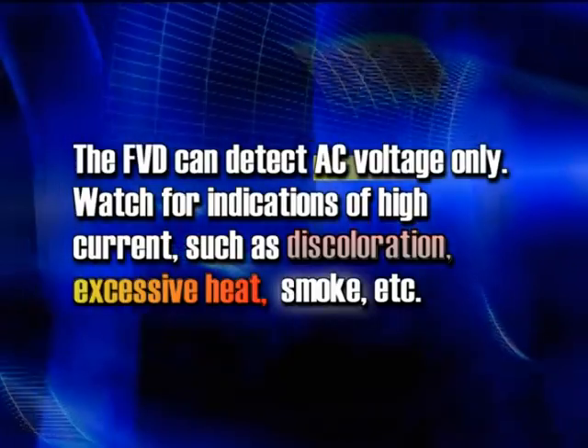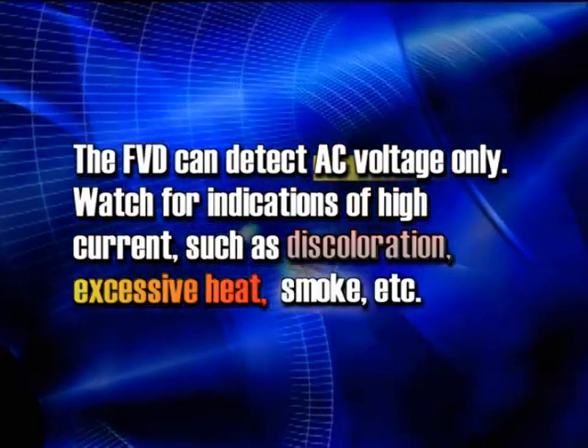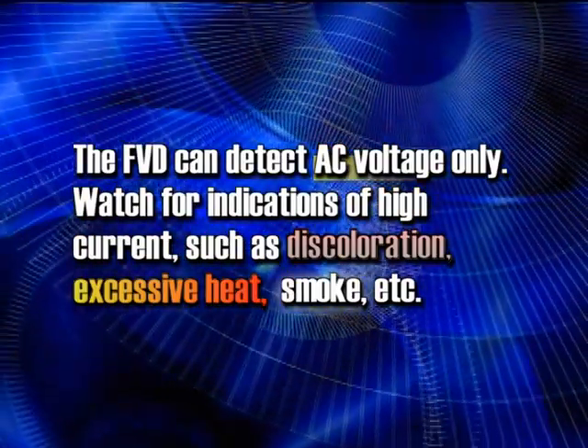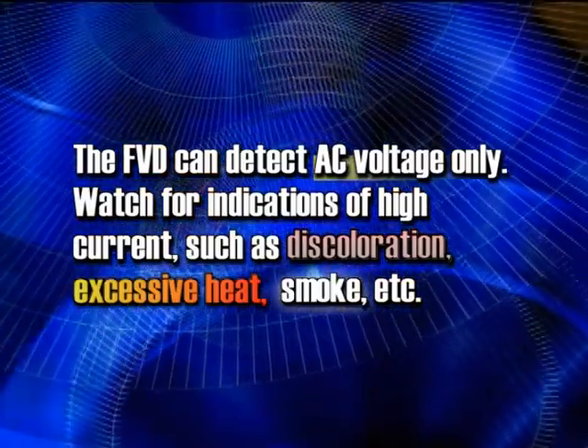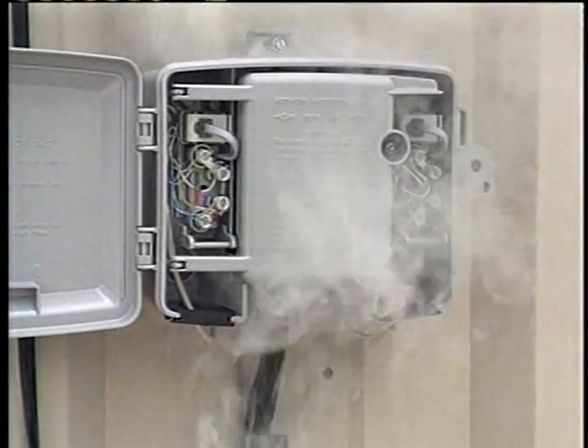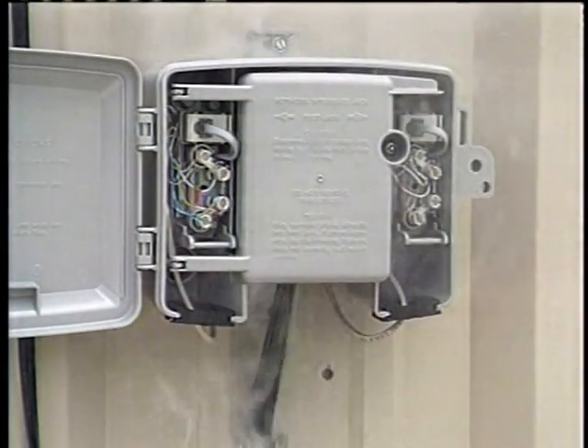The FVD can detect AC voltage only. You must always look for indications of high current, such as discoloration, excessive heat, smoke, etc. Here is an example of a high current, low voltage condition as shown by the smoking NID.